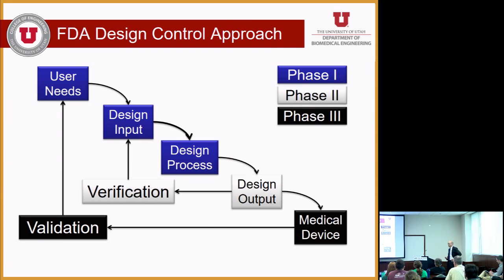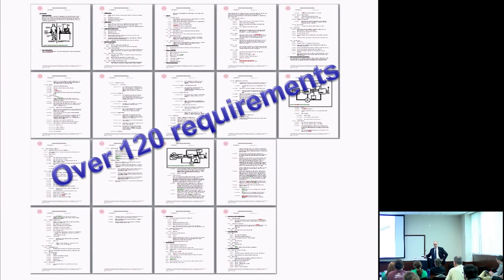And so we had several phases that we used for developing this device, but it's all about documentation and documenting what you're doing. And so our design input document for this project had over 120 different requirements. Those are requirements for patient comfort, patient safety, the monitoring of the device, the performance, power consumption, radio transmission frequency. Lots of different requirements went into this device.